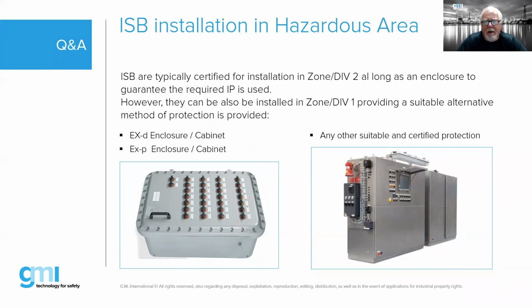When we want to mount a barrier in a zone 1 area, however, we do at that point have to install it into either a flame-proof box, or in this case, a purged and pressurized enclosure, like a PXB type purged pressurized system. So we could either do EXD in effect, and by the way, it's now going to be known as EXDB, or an EXPXB type purge system to be able to mount those barriers located in a zone 1 area.